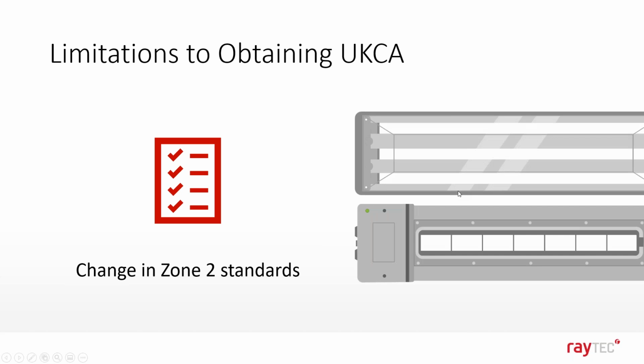In that time frame discussed, there have been changes to the Zone 2 standards. The old non-arcing EXNA conformity has now been replaced with increased safety EXEC. There are quite a few changes to these requirements, which include more stringent impact requirements: 4 joule impact on optical components, and a 7 joule impact on non-optical components. Overall, these requirements are broadly similar to the requirements of the Zone 1 product, rather than the slightly upgraded requirements from an industrial product that the old EXNA required.